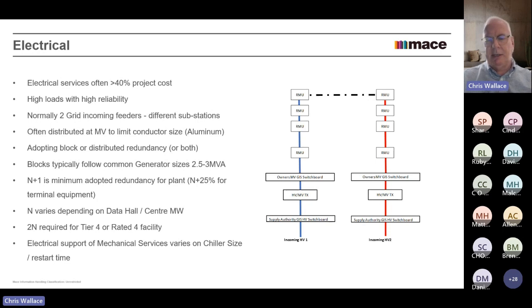And the other thing is the chillers, typically, unless you've got a chiller with magnetic bearings or some other modern chiller, will have a fairly substantial restart time. If you're not going to keep it on a UPS system, you're going to have to pump it down and rebuild it back up. And therefore, what most people do is have some form of thermal energy storage, which means basically they make and store cool water. They have a tank, normally, or tanks with a block of cool water in, and that will allow the pumps to run, because you can support pumps fairly easily on a UPS, for maybe 10 minutes. That gives the generators a chance to start and the chillers to shake themselves down and get back in working order.